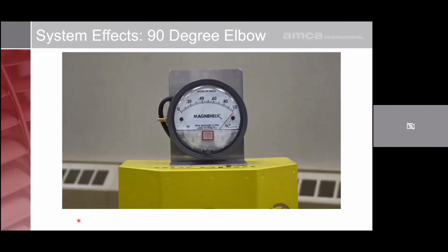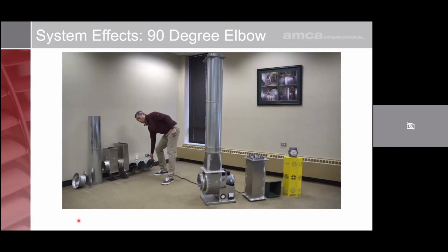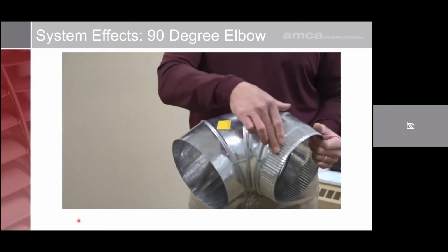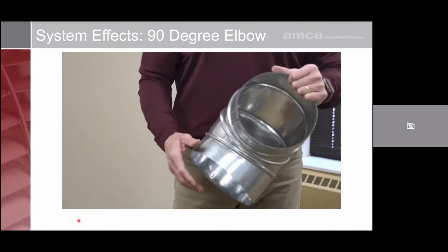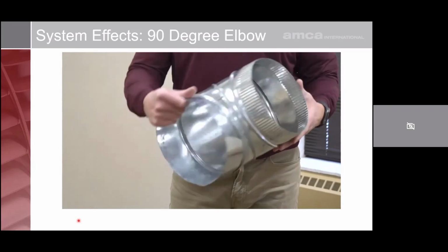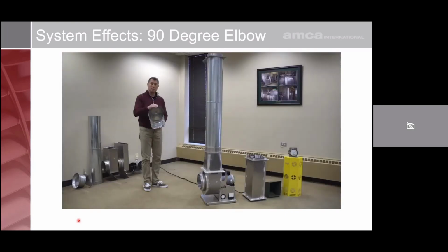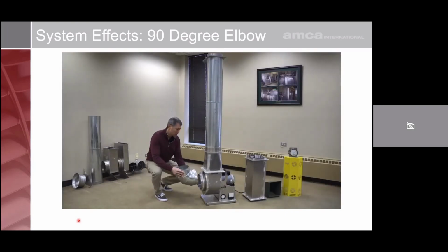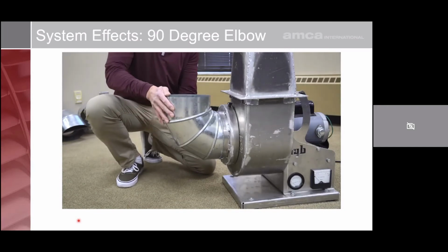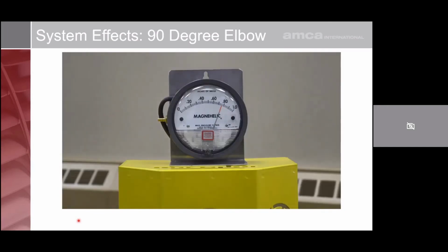So the first thing we're going to do is grab a piece of ductwork. It's a 90-degree elbow, and you can see there's no vanes inside the elbow, and we're going to see how it affects the fan's performance. So we put it on the fan's inlet, and looking at the magnehelic gauge over there, you can see that the fan performance has gone down significantly just by putting a 90-degree elbow on the inlet of the fan.